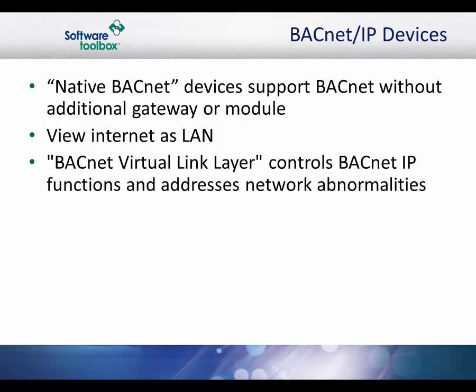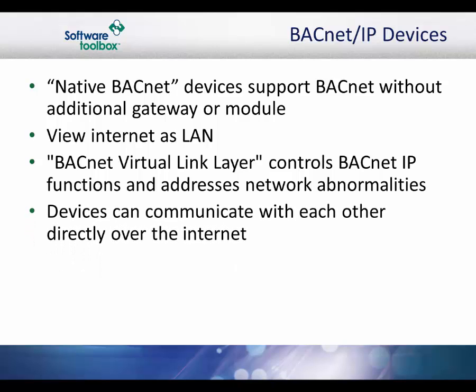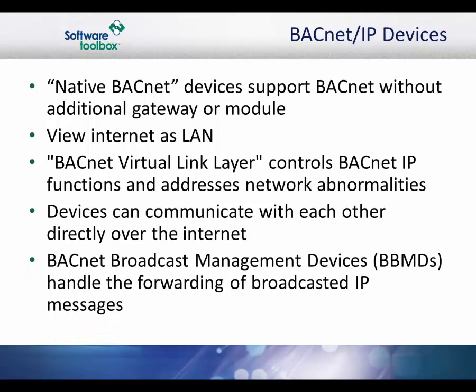The layer's control information can also be easily expanded to include almost any kind of new network technology that may surface. Therefore, a specification could be easily created to run BACnet directly over asynchronous transfer mode networks, synchronous optical networks, frame relay networks, and integrated services digital networks. This also results in heightened security and quality without interfering with BACnet's existing application and network layer protocols. BACnet IP devices can communicate with each other directly over the internet. Unfortunately, IP routers do not usually transport broadcasted messages, and so the BACnet broadcast management device was developed. These devices behave somewhat like routers, except they only handle the forwarding of broadcasted IP messages. However, this is not a significant issue because broadcasts are rarely used in BACnet.